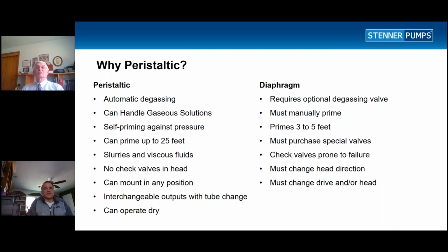So why would you want to choose peristaltic pumps over a diaphragm pump? Well, some of the main characteristics of a peristaltic are, number one, peristaltics are self-degassing. We can prime up to 25 feet. We can handle heavy viscous fluids.